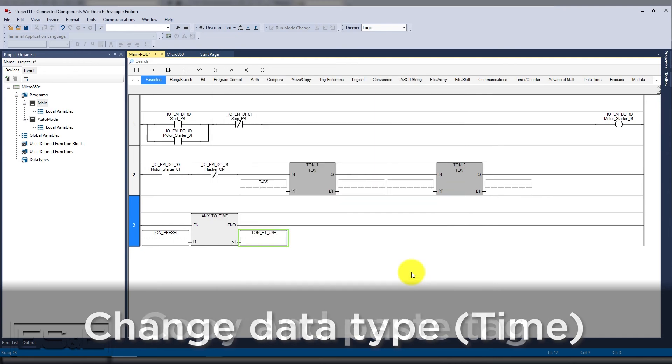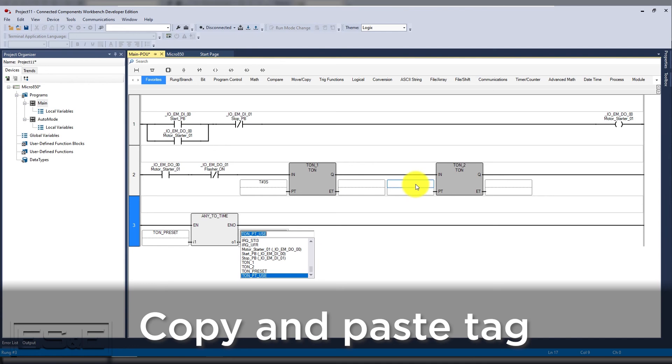Start by selecting variable selector and go back to the global variables tab. Now notice that it is not showing the tag that we just created. One of the features of CCW is it doesn't show you the tags of other data types until you click the first row that is blank. Our new tag will be timer preset use or TON_PT_use. And then we need to change the data type to time. Now you can copy the tag and select the preset and paste.